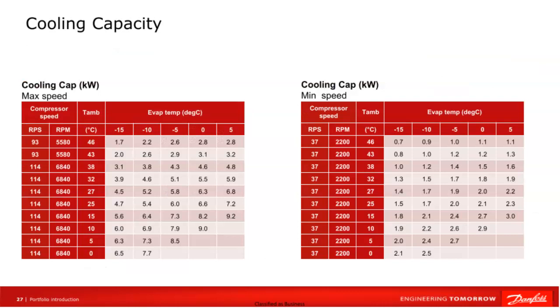This slide shows the capacity of this unit for both maximum and minimum operating speeds. We note that there is a limitation on the maximum operating speed, which occurs when the outside temperature is above 38 degrees Celsius. This results in a significant reduction in the capacity of the unit in the event of very high external temperatures. This is important information to consider when designing and installing the cooling system. Now, let's take a closer look at the operating envelope.